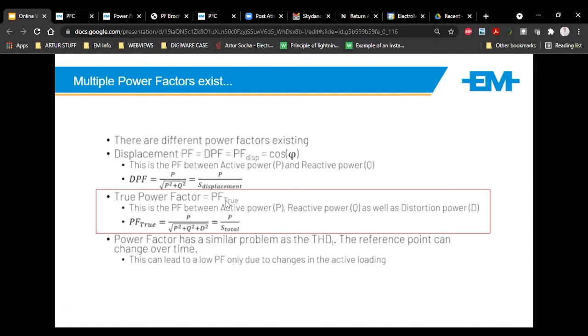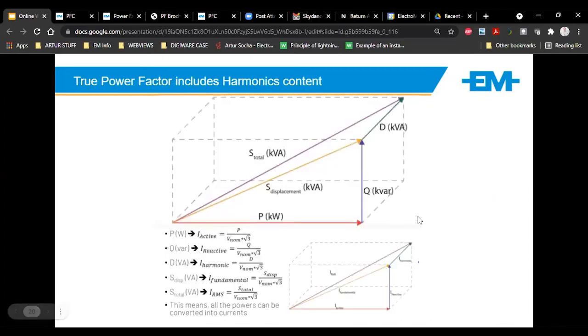which we'll briefly talk about. What is the main cause of this distorted power and how is it measured? It basically comes from a variable we call total harmonic distortion in current, and this will reduce your true PF. If we relook at the power triangle, on a normal system we had kilowatts and kVA. But true total kVA includes the distorted part of the network. The fundamental current gives displacement kVA, while total kVA is based on including the IRMS.